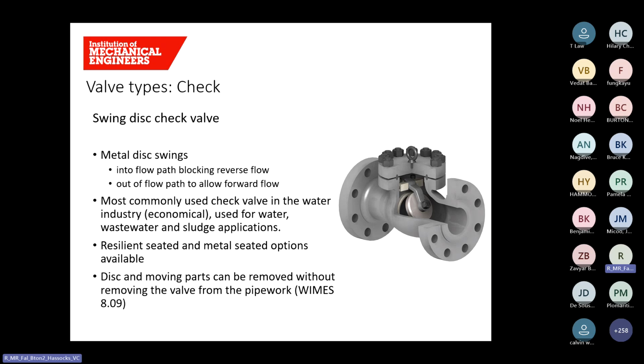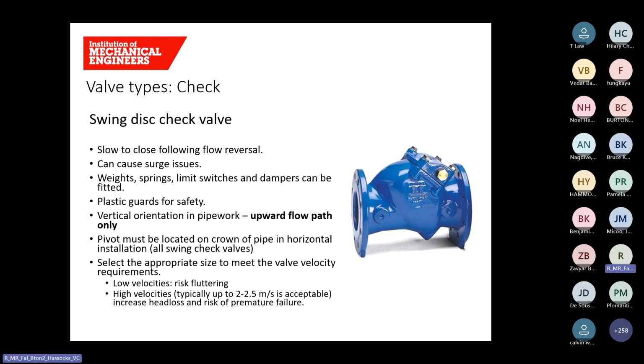It's the most commonly used valve in the water industry and can be used on clean water applications, wastewater, and also sludge. There are options to have a resilient seat or a metal seat, and the disc can be removed without having to remove the valve from the pipework. The swing disc check valve is relatively slow to operate, and this means you can get reverse flow occurring. And when there's reverse flow, the valve tends to slam shut, sending a shockwave down the pipeline, potentially leading to surge events. So to reduce the chances of this happening, springs can be installed to the valve, or levers and weights on the outside of the valve. If levers and weights are installed, then it's important to provide guarding, because it can present a hazard to people working in the area.